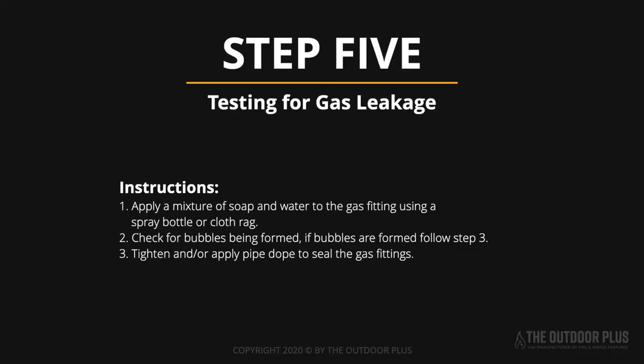Step 5. Testing for gas leakage. Apply a mixture of soap and water to all gas fittings. Only turn on your gas and check for any bubbling on the gas fittings. If there are bubbles, apply pipe dope to the gas fittings and repeat the leak test. If there are no bubbles, your fire feature is ready for use.